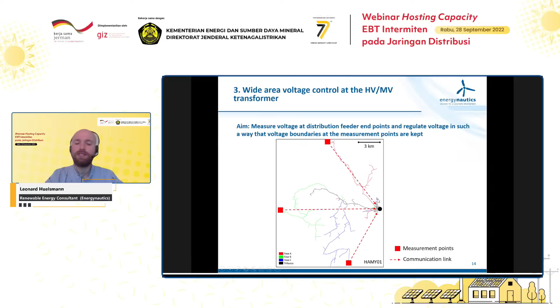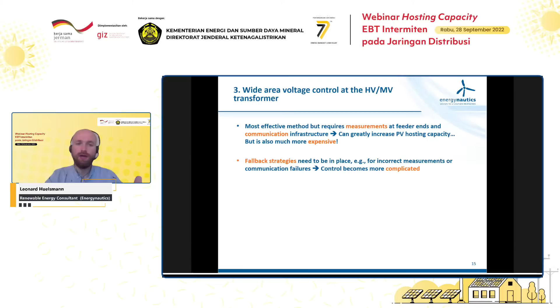And then there are options such as wide area voltage control, where you collect voltage measurements from multiple points in the system and send these through a communication link to your primary substation transformer, in order to see whether there are any under voltage or over voltage problems, and then regulate the voltage in such a way that all your voltage boundaries are kept. So this option would be much more effective. However, it would also be more expensive, because you need these voltage measurements and communication infrastructure. This is just to highlight a little bit what analysis and options you may have, giving you a few ideas about this whole topic.